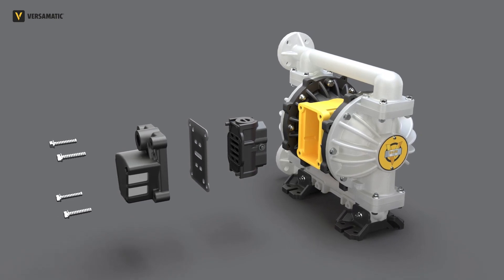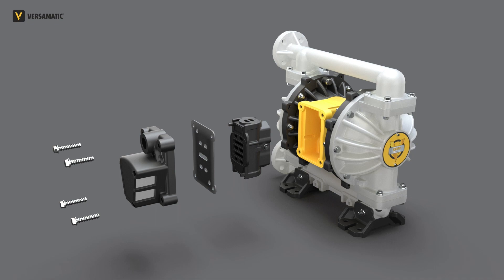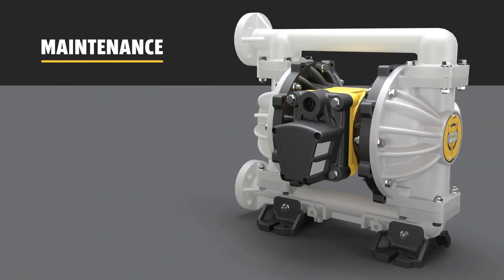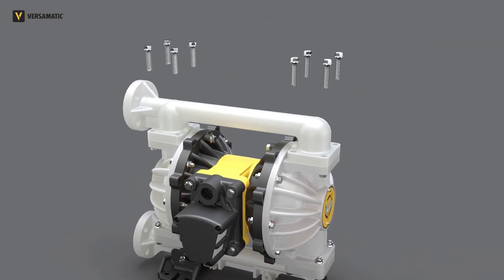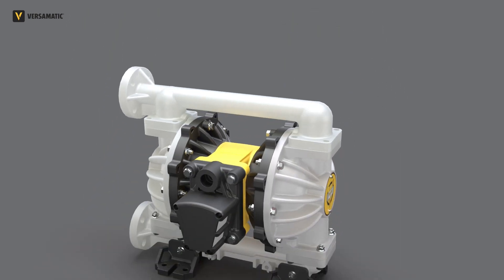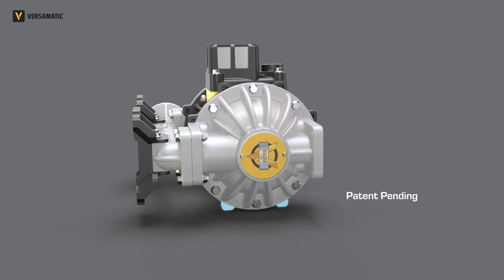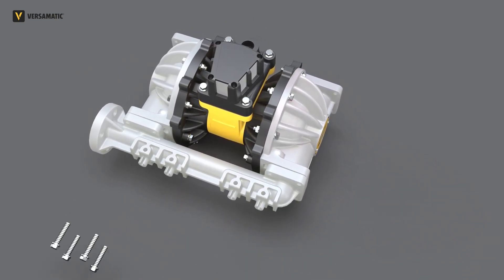Reassembling the Versamatic Valor is easier than ever. The air-side components are symmetrical and can be assembled in either direction. To simplify maintenance, all of the wet side bolts and nuts are the same size and length. We have added standoff feet to the inner chambers to stabilize the pump on the workbench during disassembly.